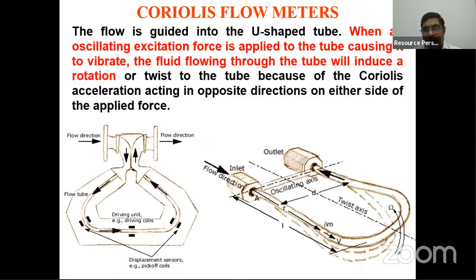It vibrates like this, set to vibrate at a constant frequency, and on both the upper side and lower side of this U tube there will be a sensor. The sensor senses the oscillation frequency.